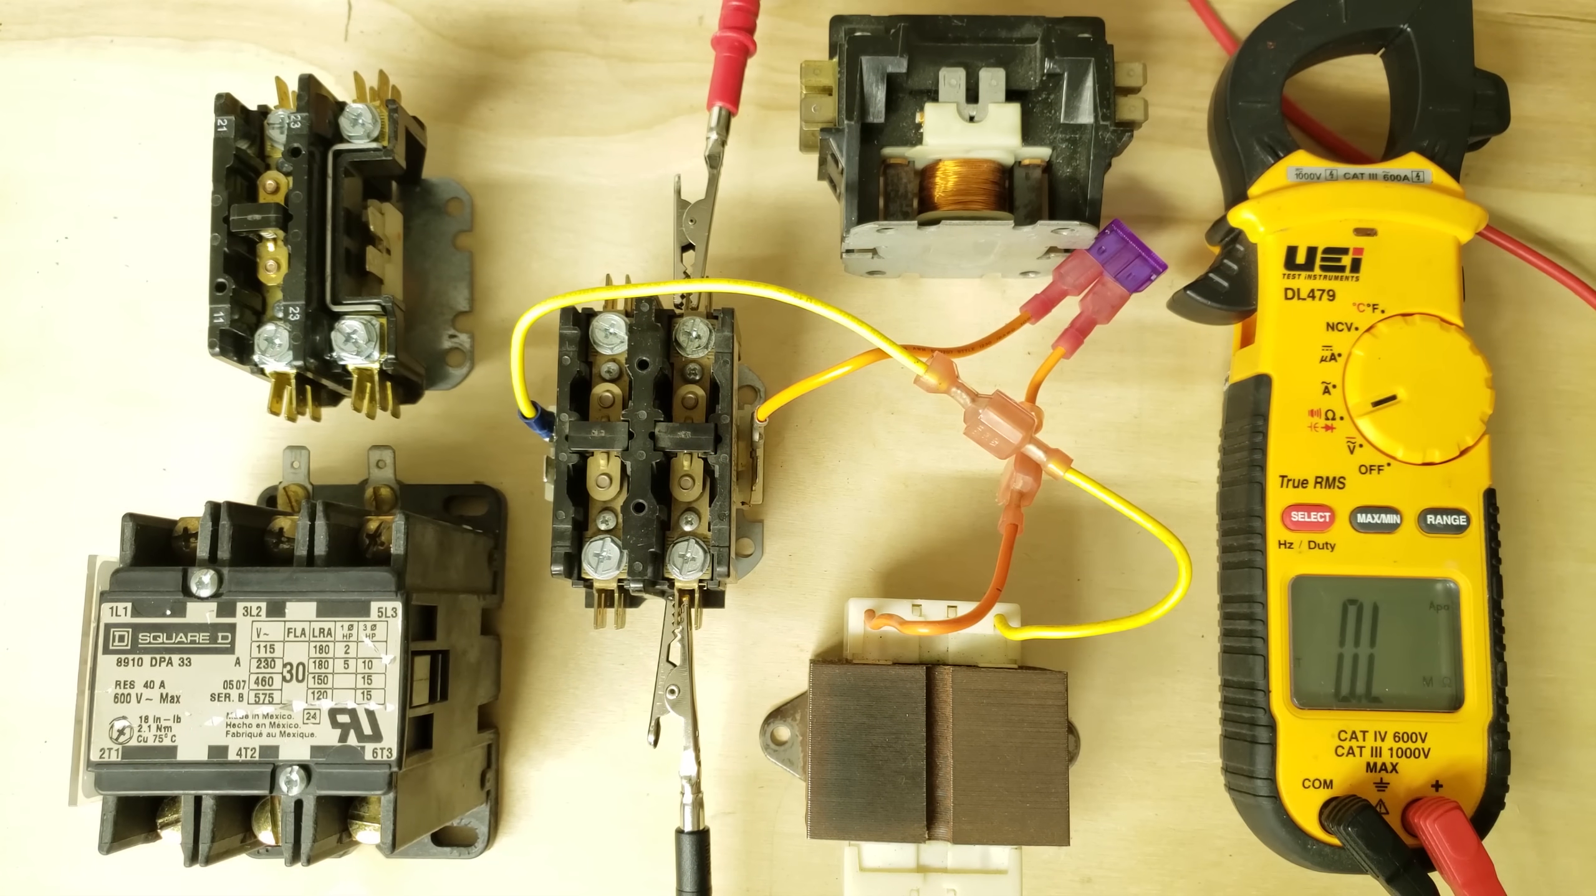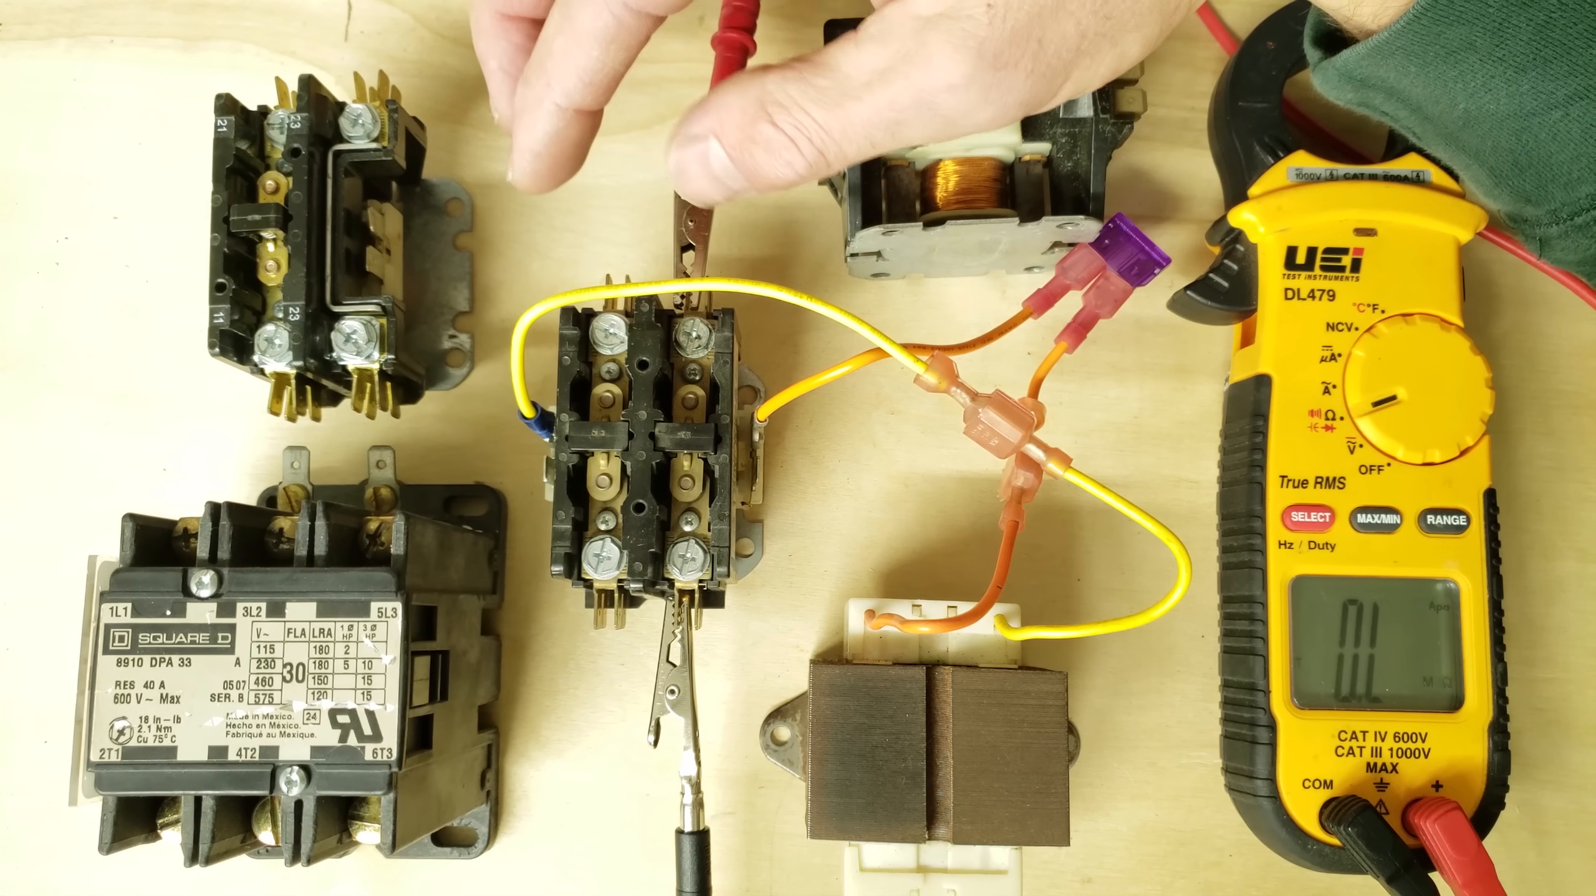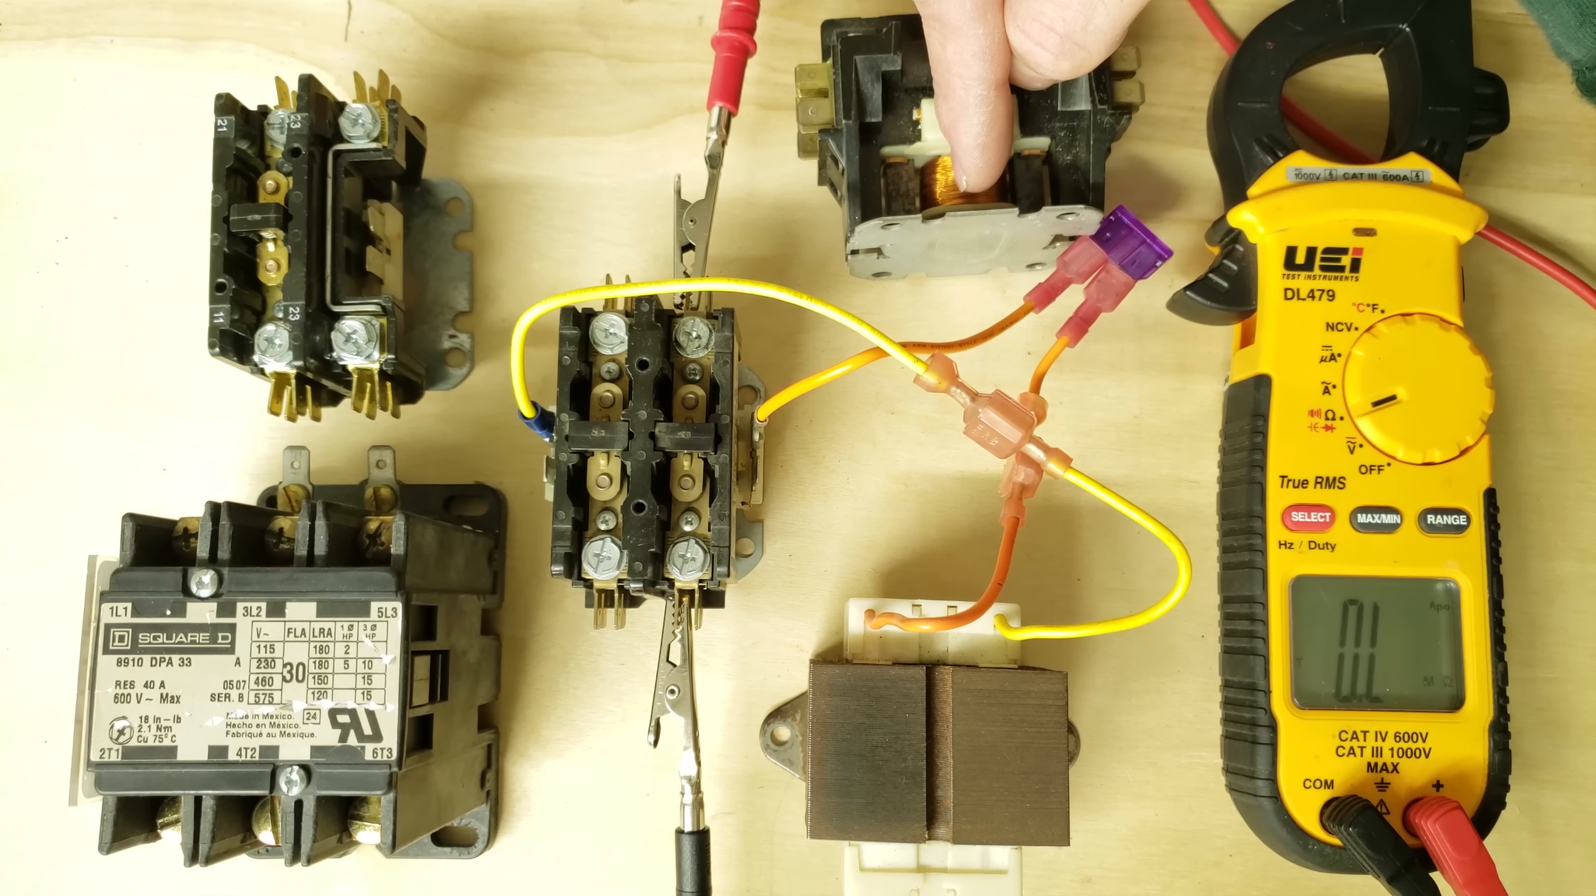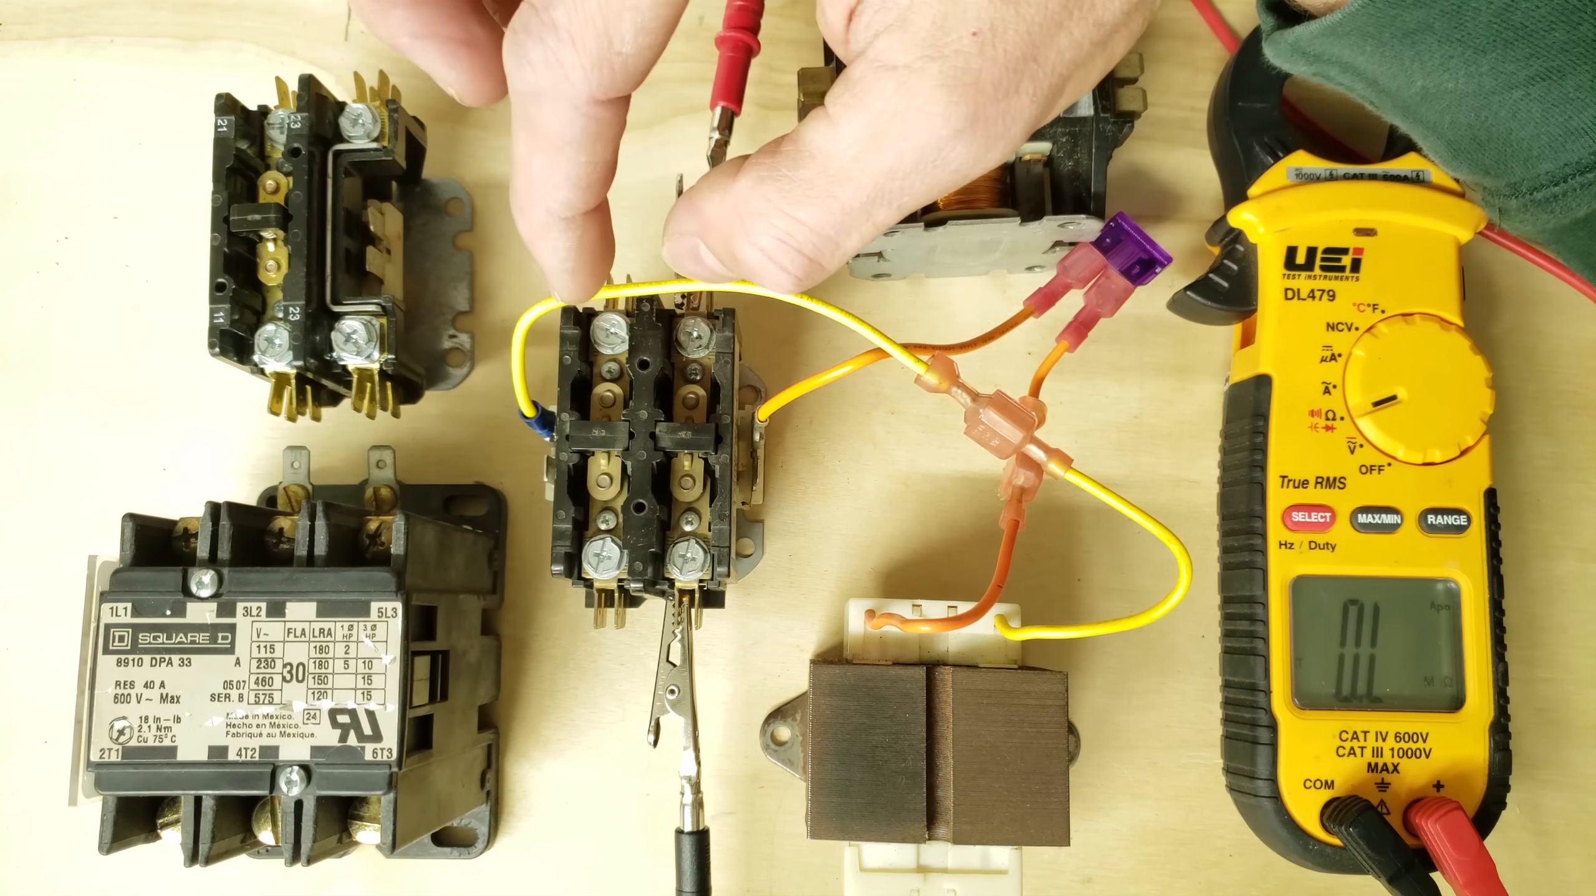Before we get started I just want to show how the contactor works and explain the differences. So in this case we have a two pole contactor so it has two sets of normally open contacts that will close when you apply power onto the coil. Here you can see an exposed coil on the side and we're just applying the 24 volts onto the side in order to allow the voltage to come across here.